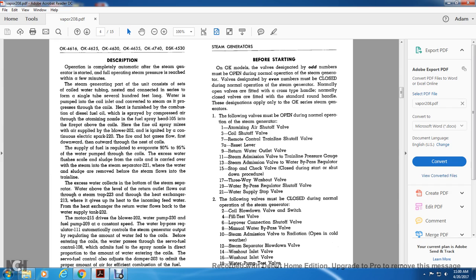through the atomizing nozzle in the fuel spray head 105 into the fire pot above the coil. The fine oil spray is mixed with the air supplied by the blower 202 and is ignited with a continuous electric spark 220. The fire and hot gas flow is first downward and outward through the nest of coils. Supply of the fuel is regulated to evaporate 90% to 95% of the water pumped through the coils.